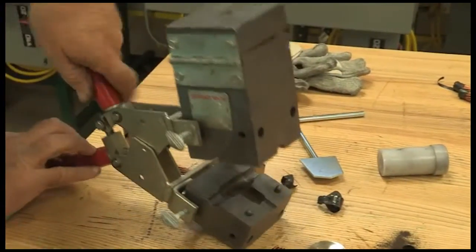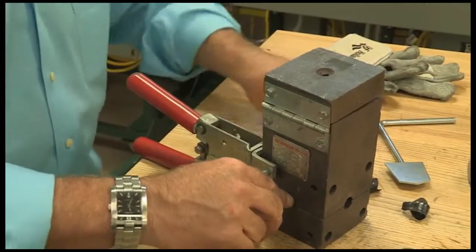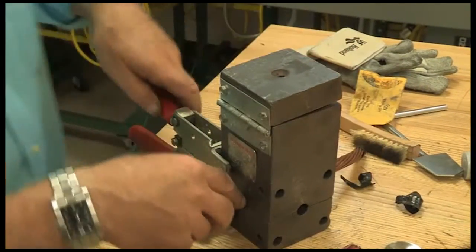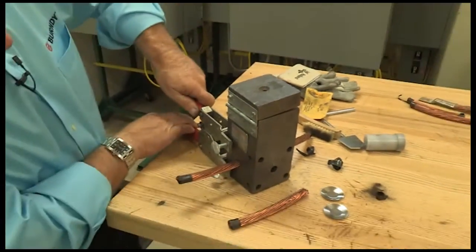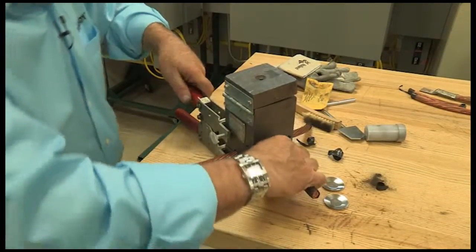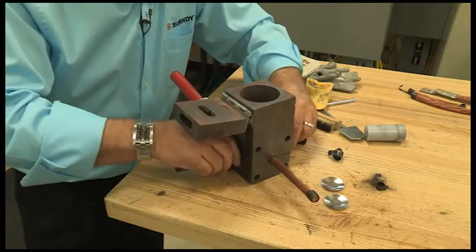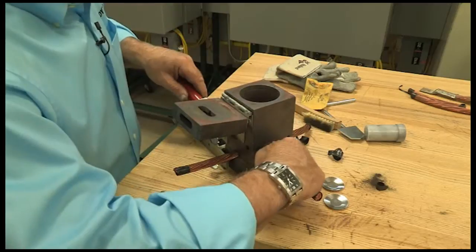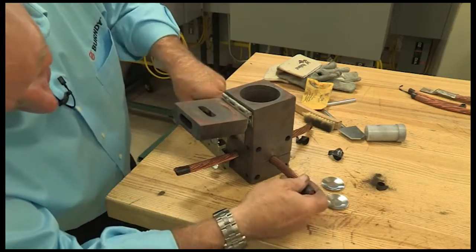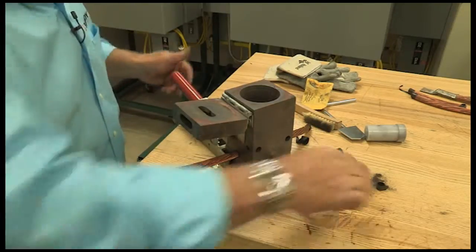Next thing we'll open our clamps so that we can position our cables. This one I'm going to actually have two different cables meeting in the center and then one tapping off. And you don't want to have them perfectly touching because we want to have the molten metal fuse between. So I'm pushing it in until it touches and then backing it off at about a quarter inch.